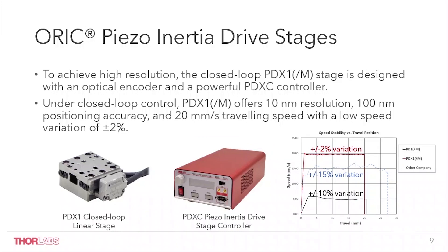To achieve high resolution, the closed-loop version PDX-1 is designed with an optical encoder and a powerful controller, the PDX-C. Under closed-loop control, the PDX-1 achieves 10 nanometer resolution.